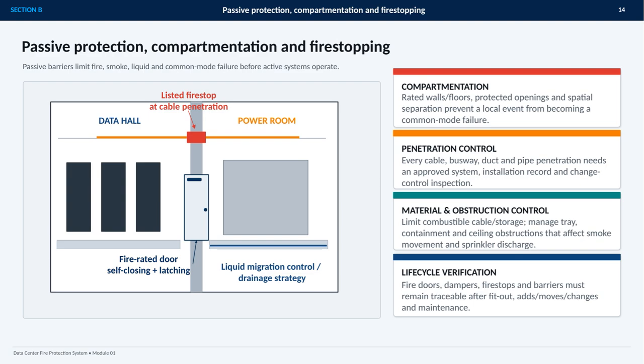Every cable, busway, duct, and pipe that passes through a barrier needs an approved fire stop system, a documented installation record, and inspection whenever changes are made. Fire-rated doors must also close and latch reliably. The strategy extends beyond fire alone.